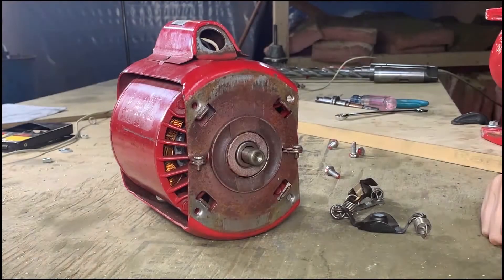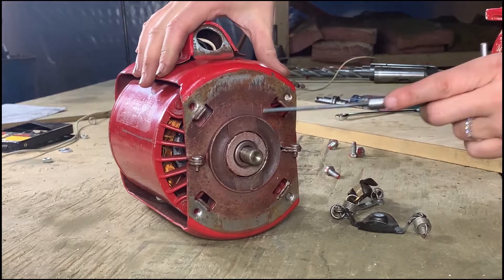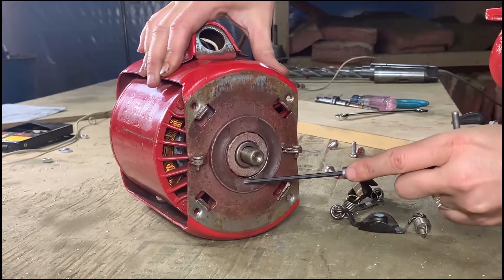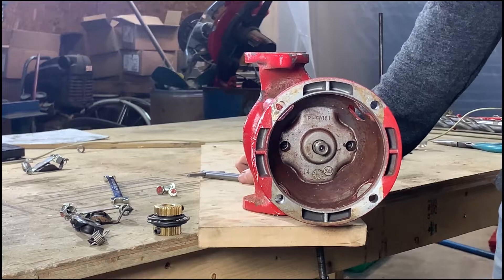One of the most common reasons the flex coupler fails is due to sagging rubber motor mounts, which causes misalignment between the motor and bearing assembly. This motor mount appears to be okay. The other reason is a seized or tight bearing assembly.